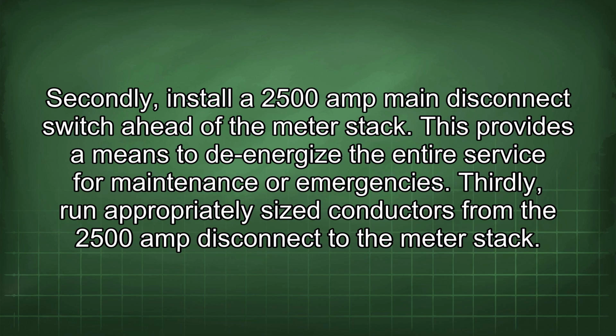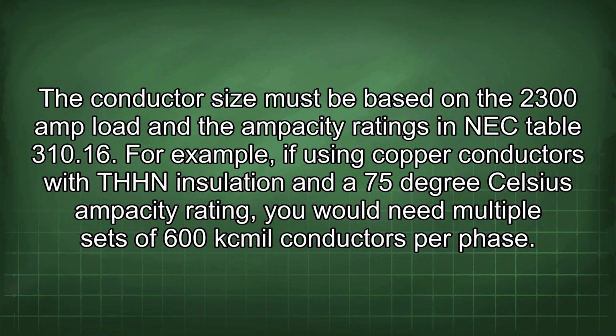Secondly, install a 2500 amp main disconnect switch ahead of the meter stack. This provides a means to de-energize the entire service for maintenance or emergencies. Thirdly, run appropriately sized conductors from the 2500 amp disconnect to the meter stack. The conductor size must be based on the 2300 amp load and the ampacity ratings in NEC Table 310.16. For example, if using copper conductors with THHN insulation and a 75 degrees Celsius ampacity rating, you would need multiple sets of 600 kcmil conductors per phase.